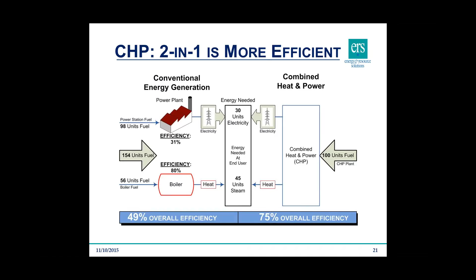Just a quick note on terminology here. Most of our CHP systems are sized according to their electrical output, but we want to caution you to think of electricity as a happy byproduct of this system. One of the most important parts of preserving the economics of a CHP system is to have an appropriately sized unit. Typically, the thermal need of most facilities that we see is a little bit less than the electrical need, and so you'd want to be what's called thermal following. You want to size according to the thermal needs and then get as much electricity out as you can at the same time.